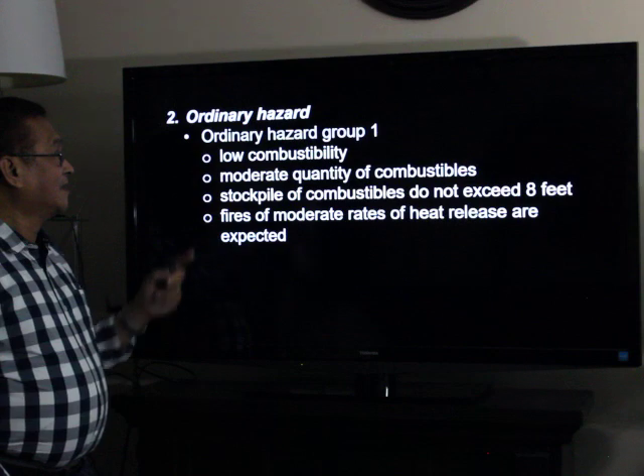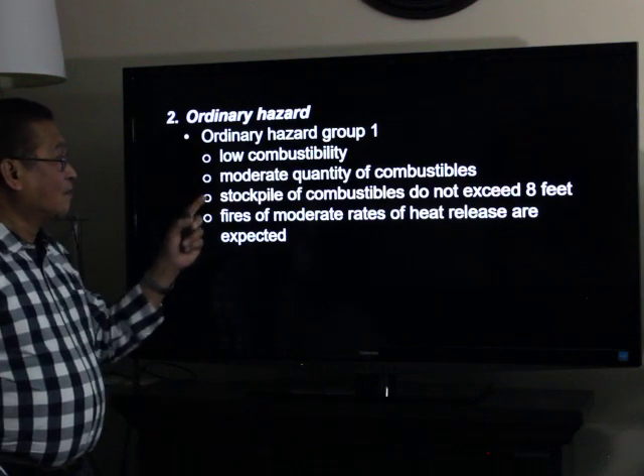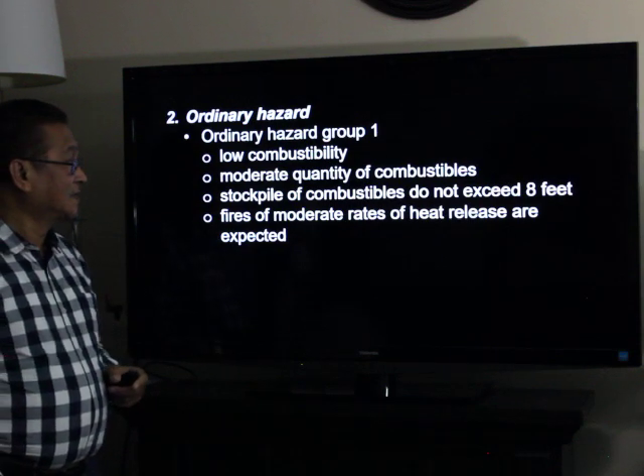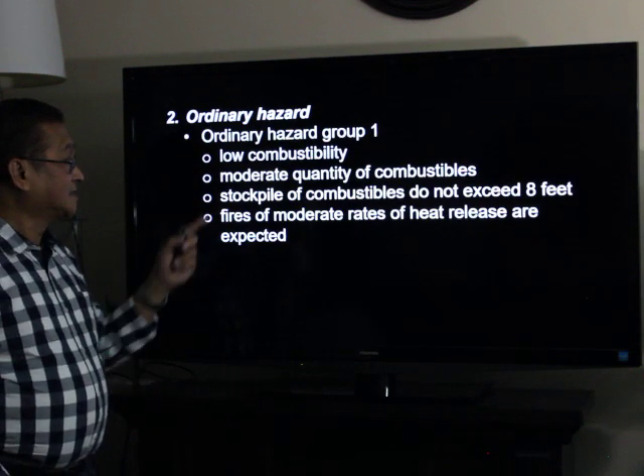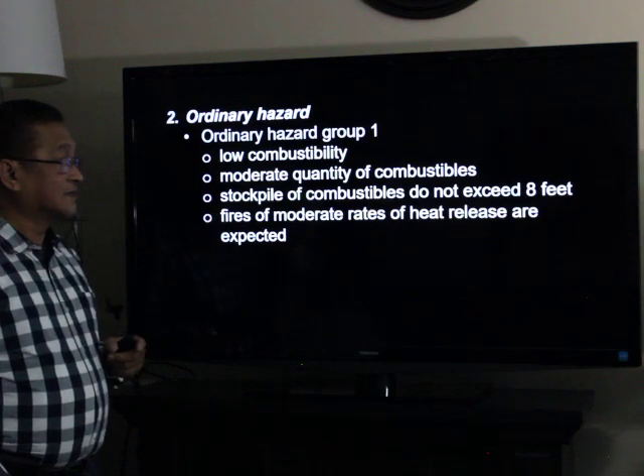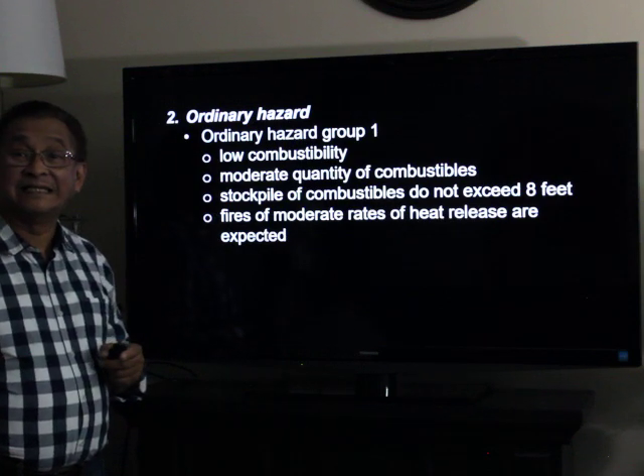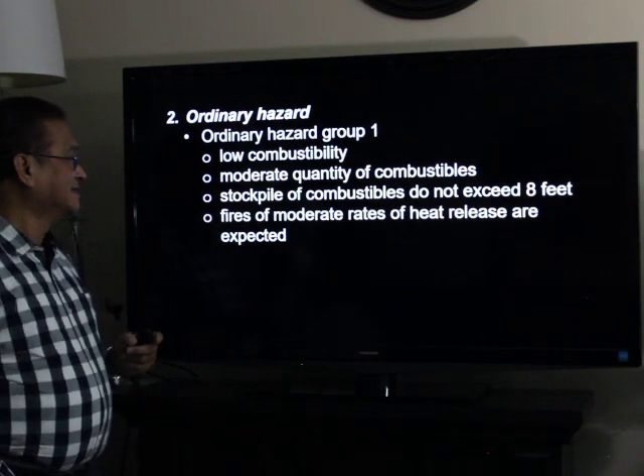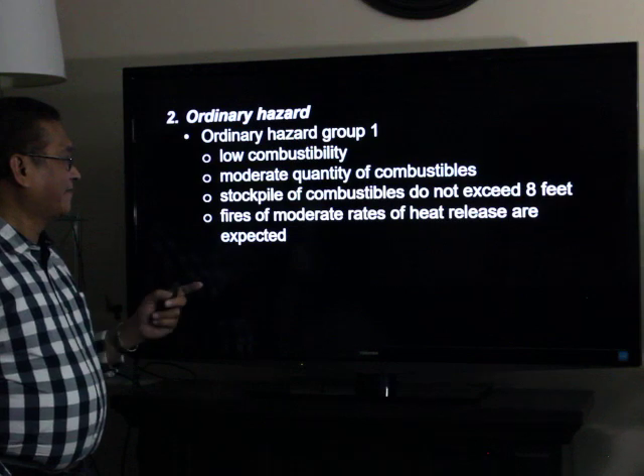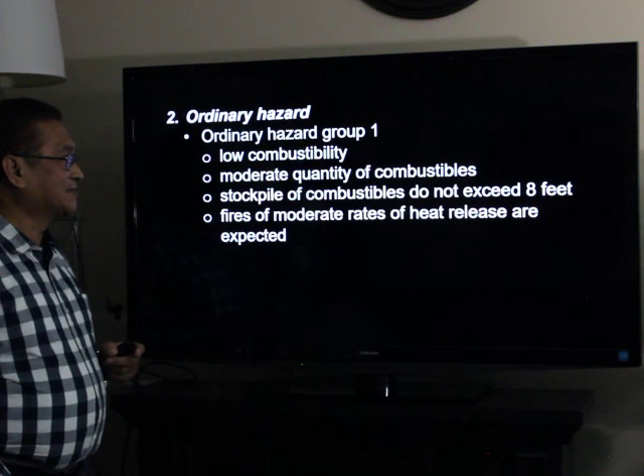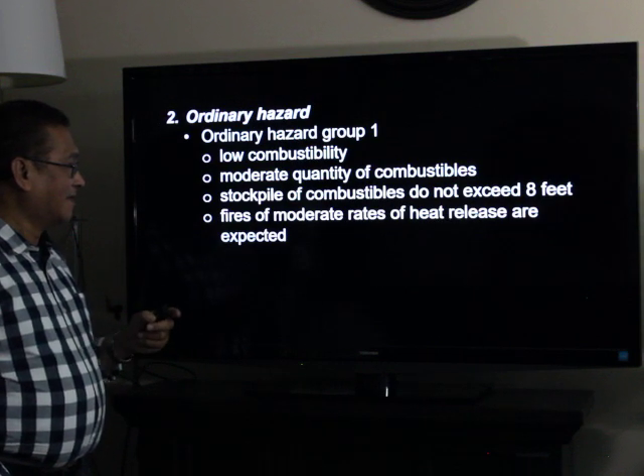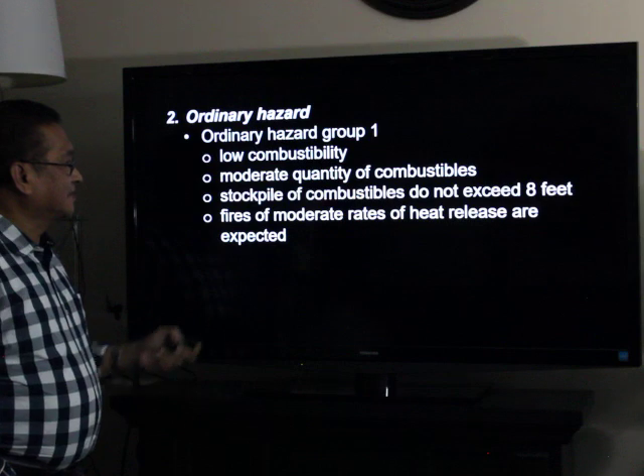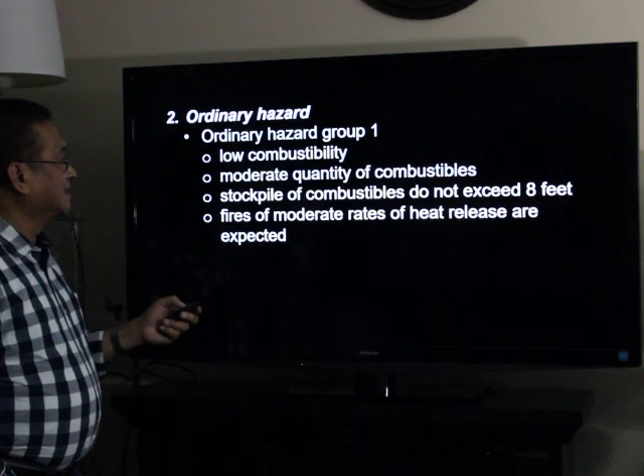For ordinary hazard group one: low combustibility, moderate quantity of combustibles, and stock piles of combustibles do not exceed eight feet in height. Fires of moderate rates of heat release are expected.